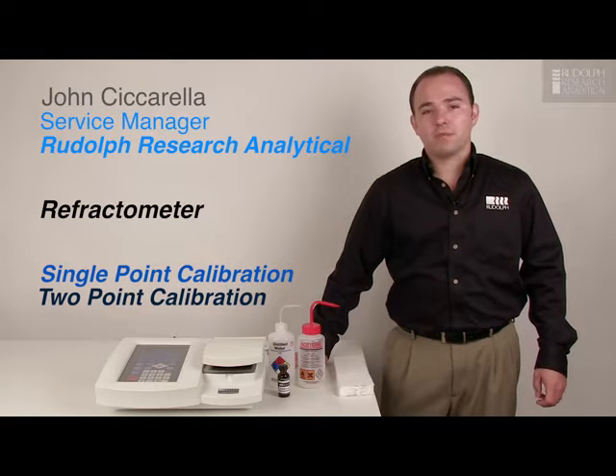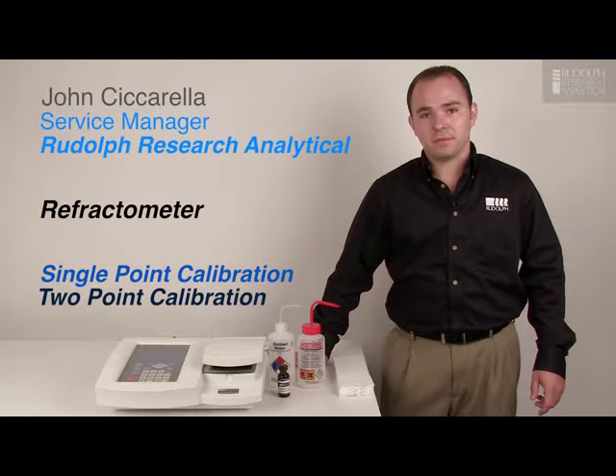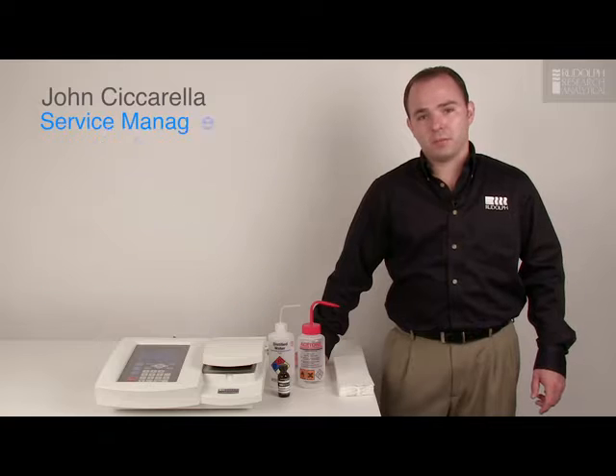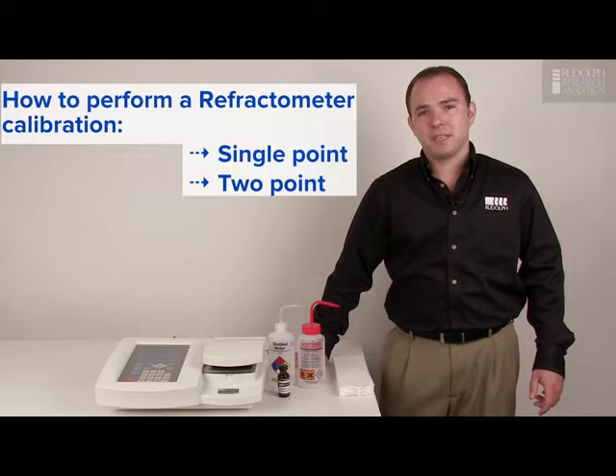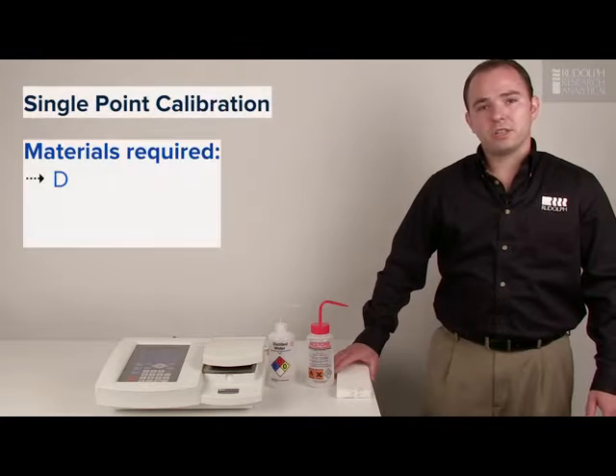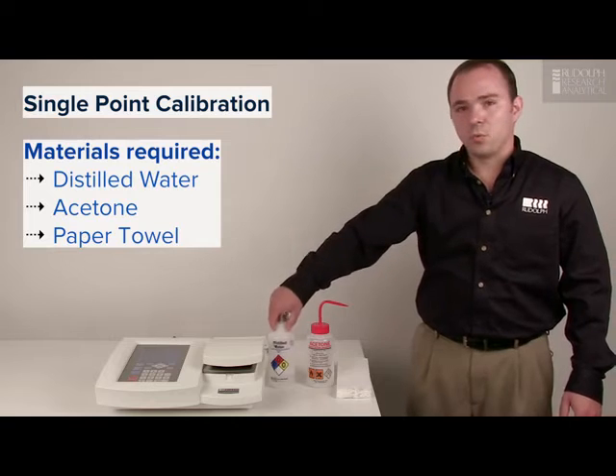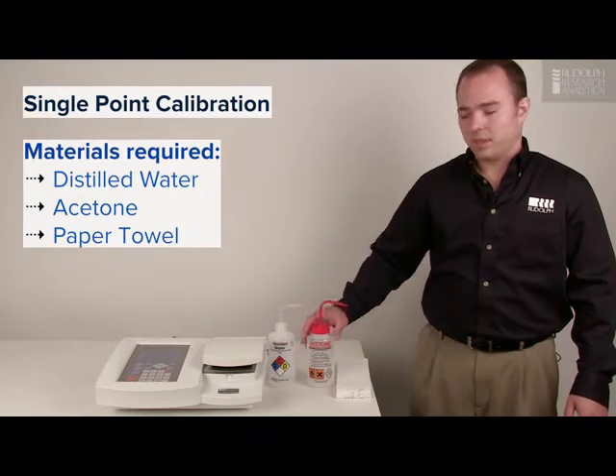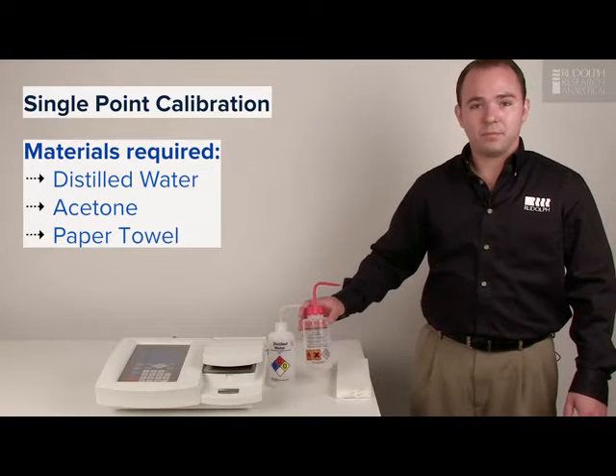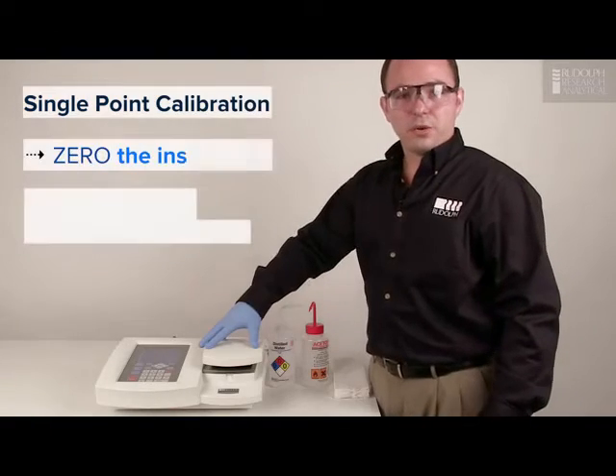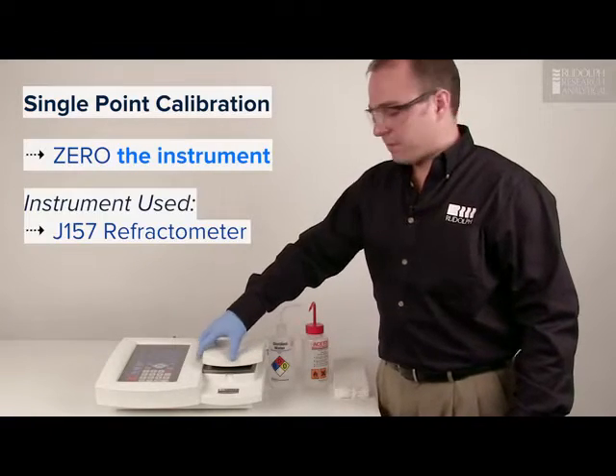Today I'm going to show you how to perform a calibration on a refractometer. There are two ways of performing a calibration on a refractometer: a single point calibration and a 2-point calibration. Today I'm going to show you how to do both. For a single point calibration, you're going to be using distilled water and acetone, or any organic solvent to clean the prism. We're going to be first zeroing the instrument on a J157.